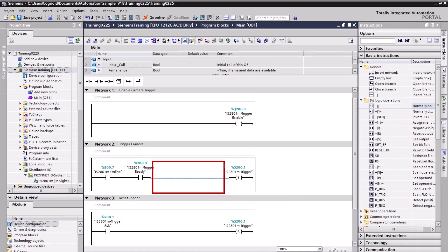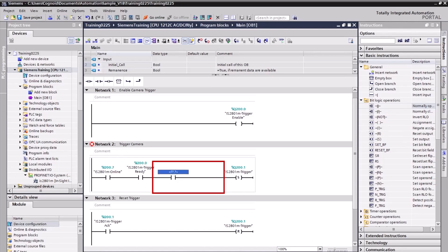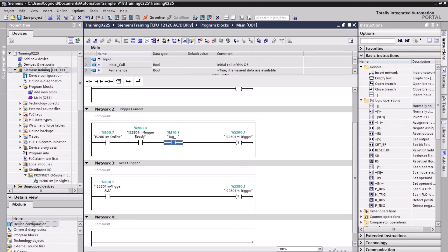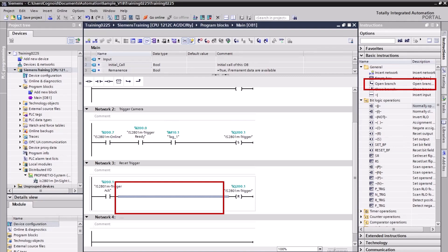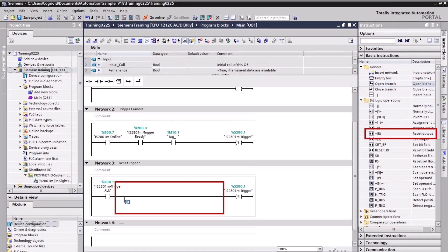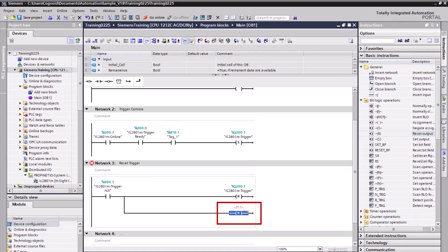Select rung 2 and double-click a normally open contact to add to the rung. Double-click the question mark and enter M10.1 in the field — a new memory bit is added. Select rung 3 and double-click an open branch to add to the rung. Double-click Reset Output to add to the branch, enter M10.1 in the field, select the memory bit tag, and press Enter. This will reset the output.